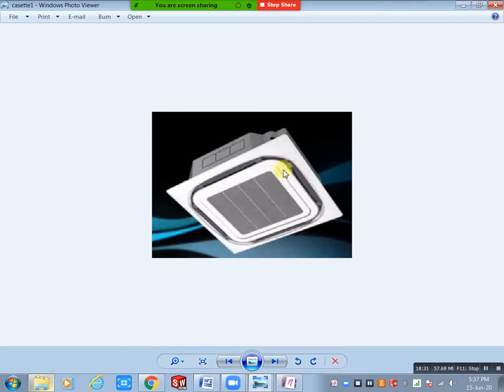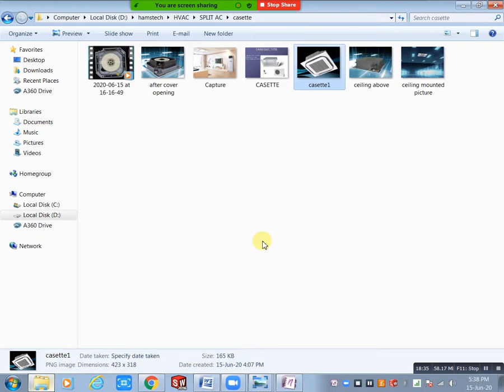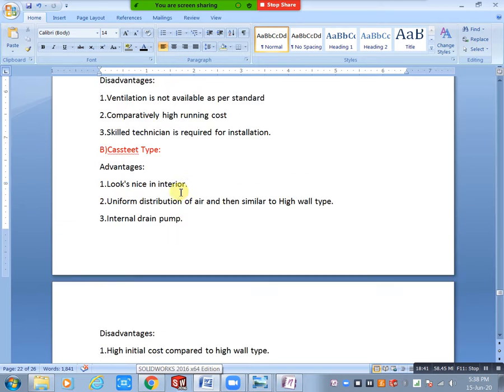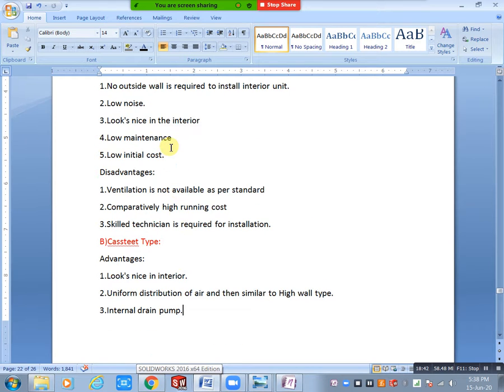Regarding internal drain pump: in high wall type, we need to add a PVC drain pipe and also a U-trap to avoid bad smell. But for the internal drain pump in cassette type, no U-trap is needed — directly connected to the drain pipe.